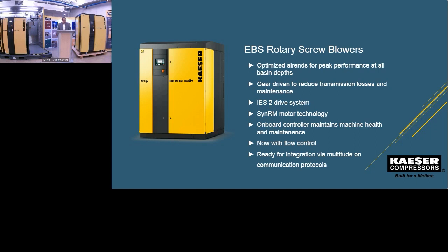Something new that's on here, of course, the controller has various control modes within it that you might need, pressure control, speed control, but something new on our PD units is the flow control. So I mentioned before, there's a host of sensors on there. So if you're monitoring your mass flow into your basins and you want to increase or decrease the amount of SCFM coming into your basins, you can then provide that flow to the machine, and it utilizes those sensors inside to calculate if the machine needs to speed up or slow down to provide you your mass flow. So this is something new they're offering with this EBS unit, and of course this is also available on all of our complete machines with the Sigma Control too.